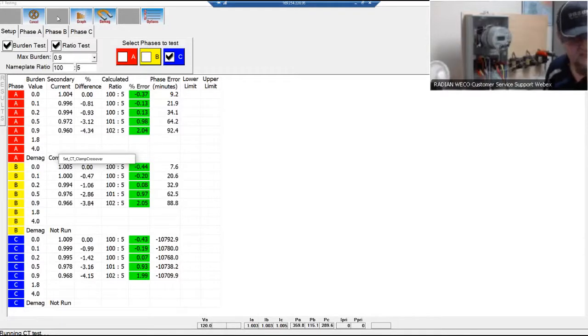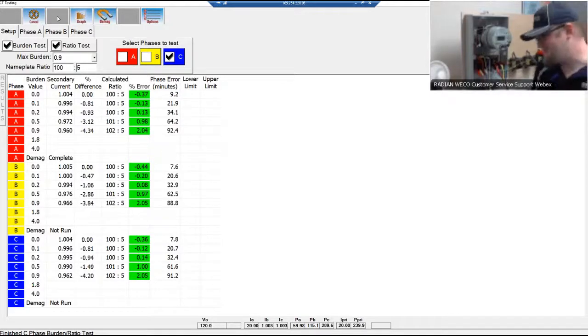So it's looking for the clamp again, found the clamp, and now it's going to run the C for C phase. So you can see the results came back a lot better than if I flipped the probe. Now they're all kind of unified, and if we look at the results here, the results after the test are shown at the bottom of the screen.